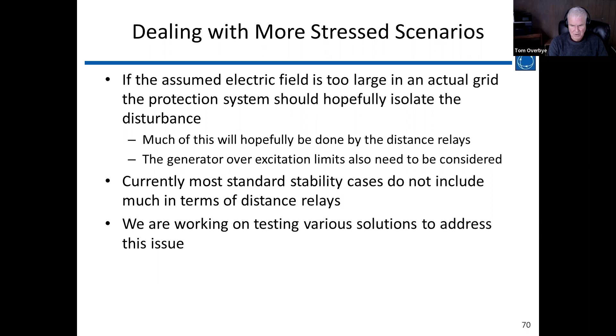Dealing with more stress scenarios: if we go above 52 volts per kilometer, this grid will not solve, it will have a voltage collapse. Would that actually occur in practice? No, because the protection system would come into play. If you've got depressed voltages and high currents, that's going to look to your distance relay like a fault. So we think going forward we need to be augmenting the grids with some of the protection system, particularly the distance relays. They're not typically included in stability studies, but that's something as an industry we might want to include. We do have ways in PowerWorld to set up kind of generic distance relay protection, and that's the next step as we go forward with these studies.